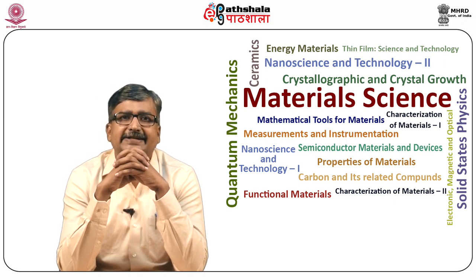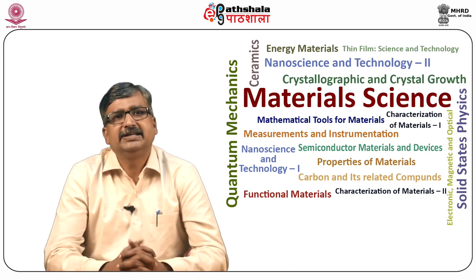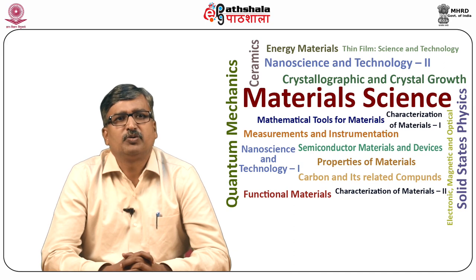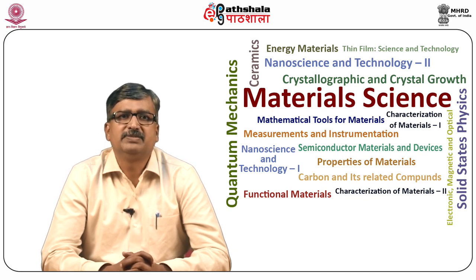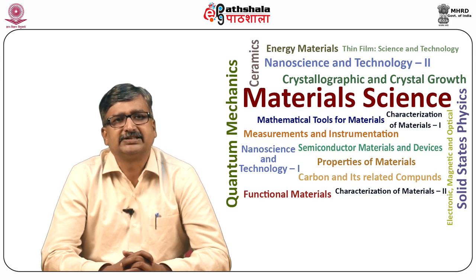The scanning electron microscope is used for observation of specimen surfaces. When the specimen is irradiated with a fine electron beam called an electron probe, secondary electrons are emitted from the specimen surface. The topography of the surface can be observed by two-dimensional scanning of the electron probe over the surface and acquisition of an image from the detected secondary electrons.